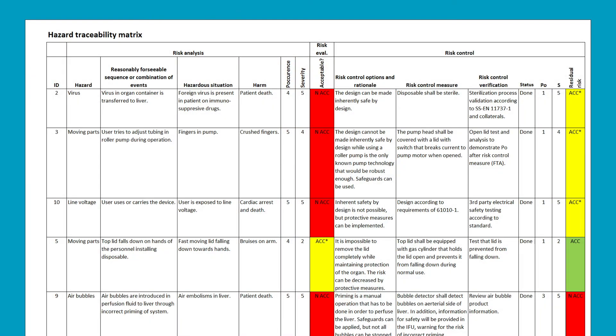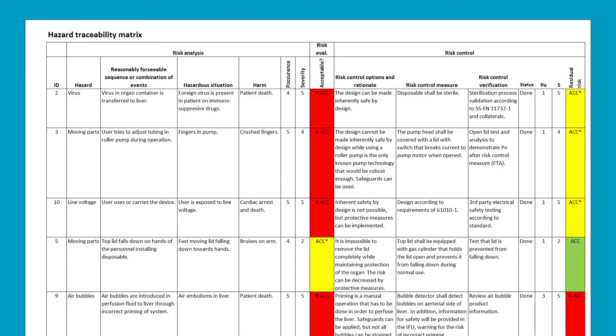So what is risk management? Many of us would think of a table similar to this one when thinking of risk management, and this is indeed a very important part of it. This table is where you would document the hazards, harms, estimate risk, and define how to reduce risks. Some people would refer to this as the risk analysis or an FMEA — I call it a hazard traceability matrix.